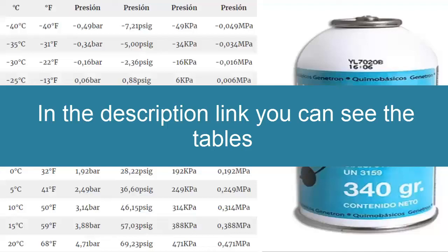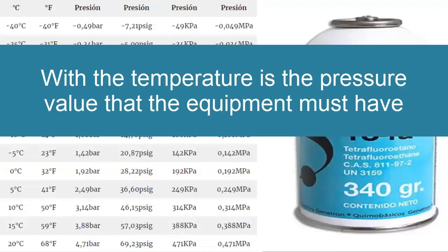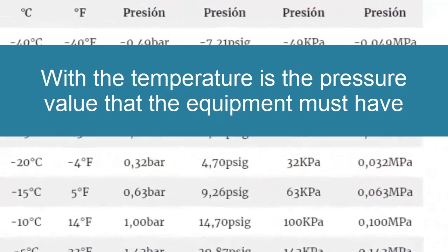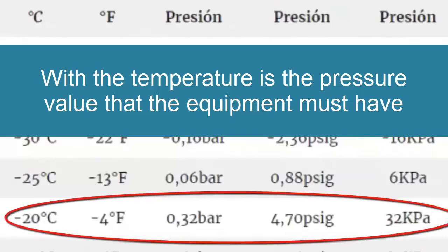The most used R-134A refrigerant gas pressures are: 1. To achieve a temperature of minus 20 degrees Celsius in the evaporator, equivalent to minus 4 degrees Fahrenheit, a low gauge pressure of 0.32 bars is needed, equivalent to 4.70 PSIG or 32 kilopascals.